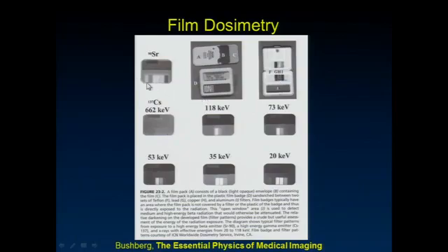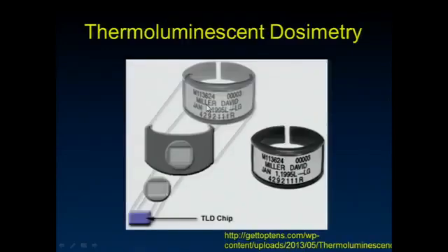And so you notice you've got this variation in exposure on the surface of that. With low energy, some of that metal had really great stopping power for those low energy X-rays. And as you got higher up, notice that they didn't have very good stopping power at all. So by looking at the variation of exposure, you could get a rough idea of what the average energy of radiation exposure was. And then by looking at overall, globally, how exposed this piece of film was, you can get an idea of the total amount of that particular type of exposure.